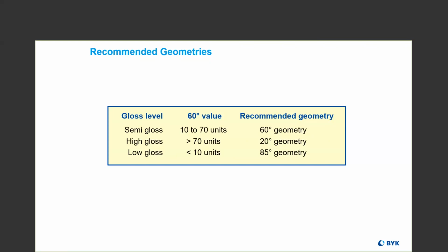If we're talking plus or minus 2 gloss units, that would be an overall tolerance of 4 gloss units, and so we'd say the uncertainty should be, in that case, plus or minus 2/3 of a gloss unit is what I should say. Okay, narrow your tolerance down by 1/3. So can I add to that?